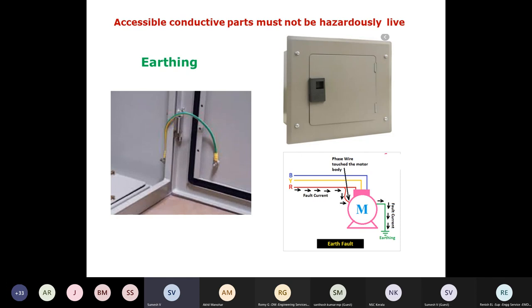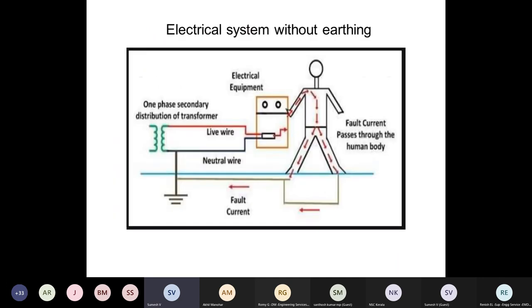The door of every distribution box is to be earthed using this flexible connection. Now this is the case of a motor. If any leakage comes to the motor body, and the motor is earthed, that fault current will flow to the earth through the earth connection, and it will operate the protective device, clearing the fault. This is the earthing technique.